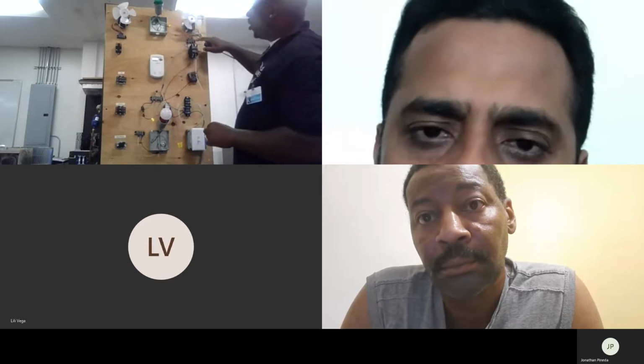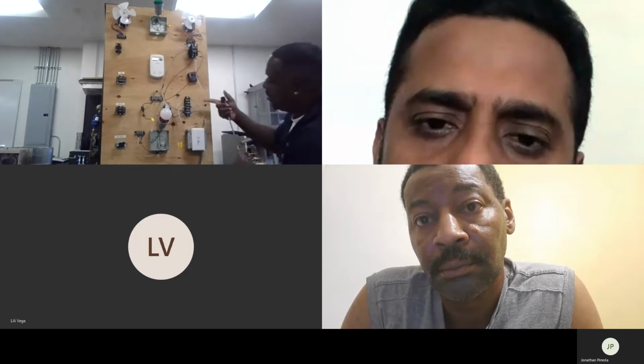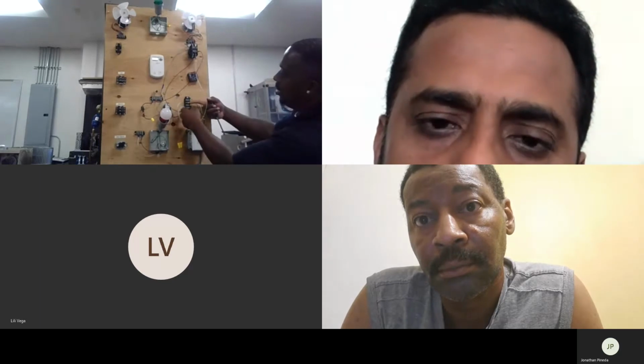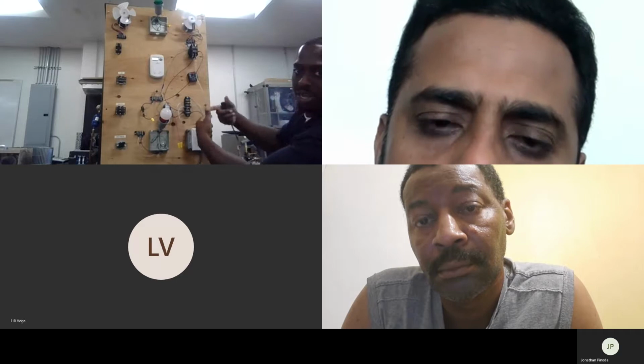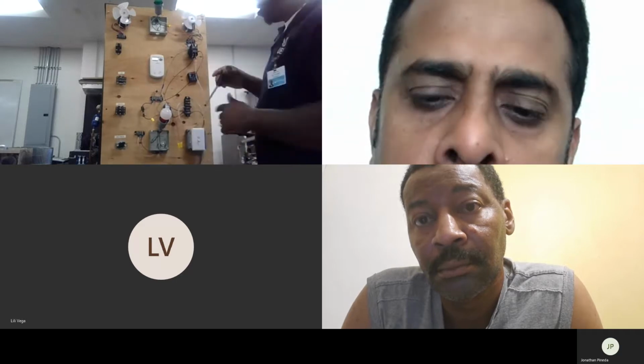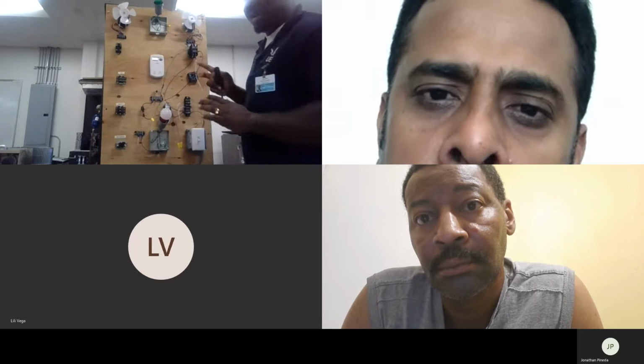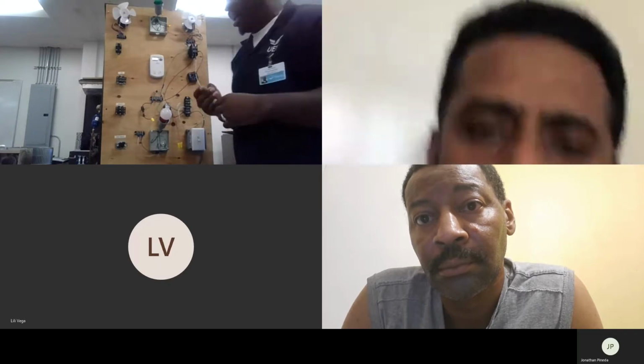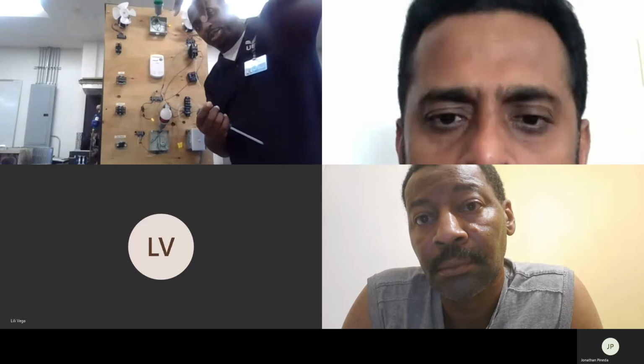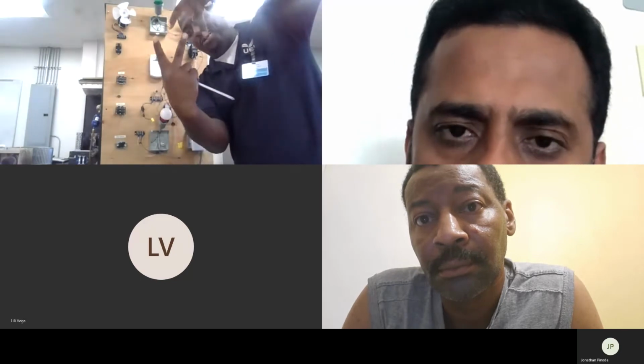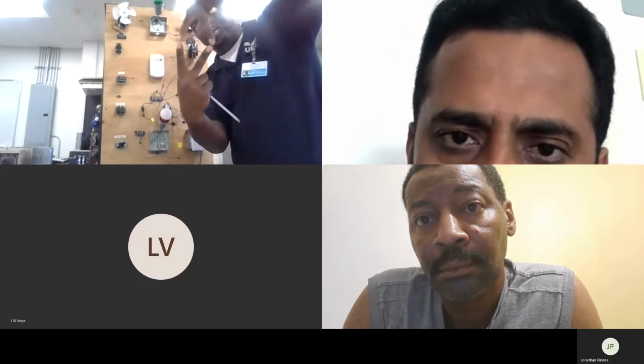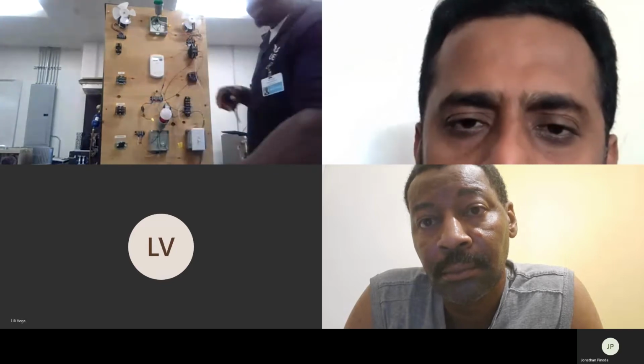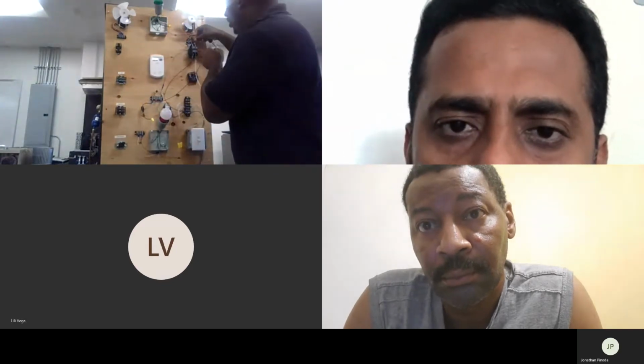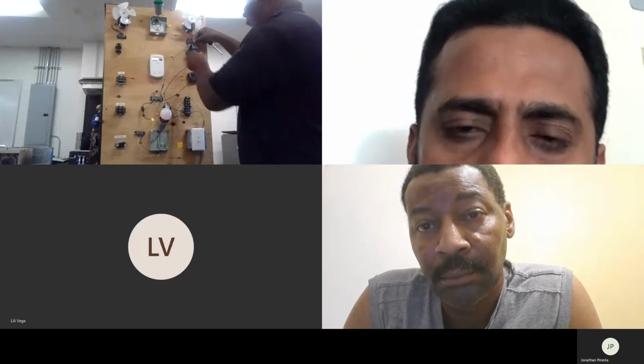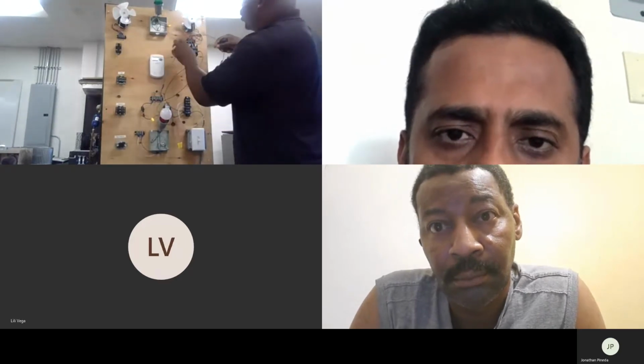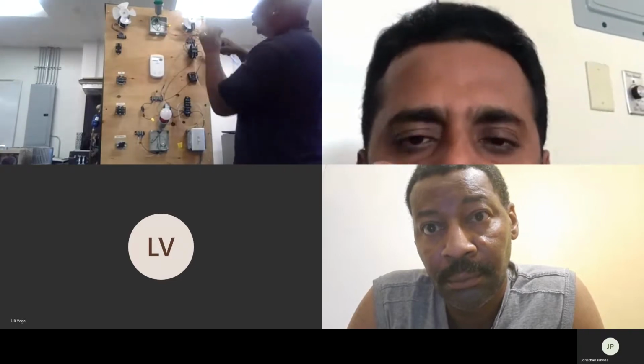And then my L2 is going to go to that third screw. Because remember, if I got something connected here, but the other one connected here, these two things ain't matching up. I wanted to point that out because I had a few students do that - they had everything hooked up right, they couldn't figure out why the fan wasn't running, but they had the fan wires connected to 2 terminals up here, and the other ones connected to 2 opposite terminals, and there was no continuity. So just make sure you connect to the same contacts - L1's going to this screw, L2 is going to go to this one.